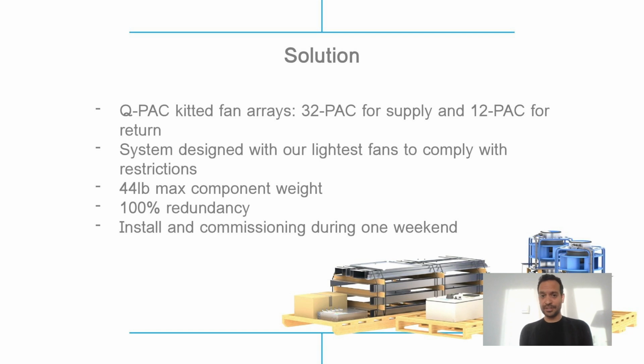We actually used our lightest fans on the supply side that were only 44 pounds, so way less than what they actually needed. We gave them 100% redundancy, so this time they are not going to be worried when one of these fans failed. The system is going to keep working and delivering the design CFM, and they will have time to replace that fan. Just because of their remoteness, they got a spare fan for both their supply and return. They actually got spare components for everything, including controls and everything else, just because they didn't want to wait. It's a remote location, so they didn't want to wait for shipping time.